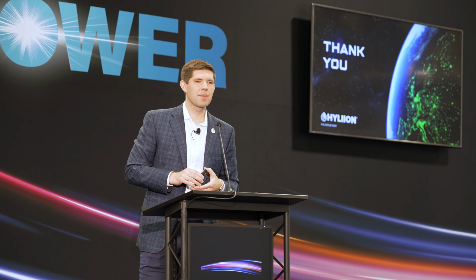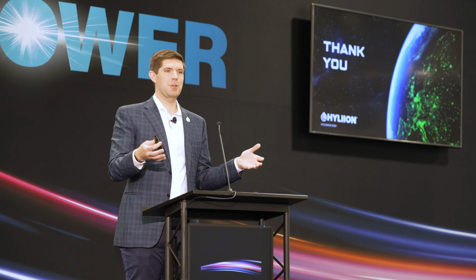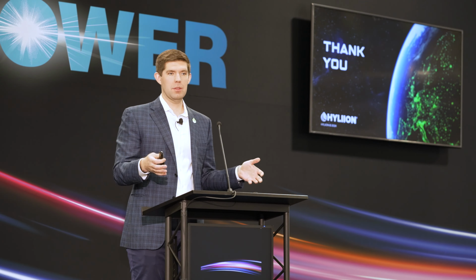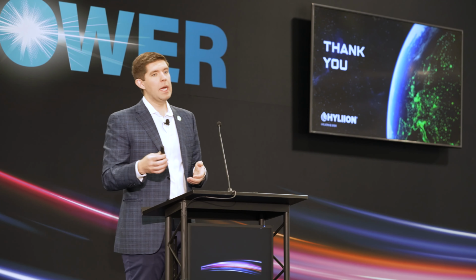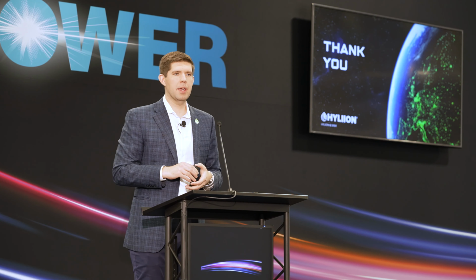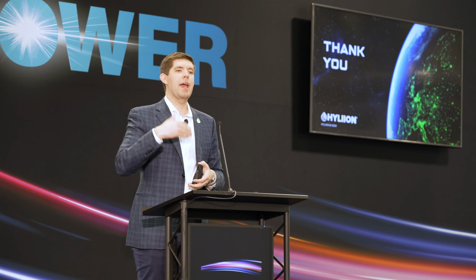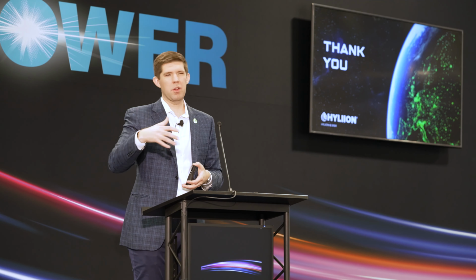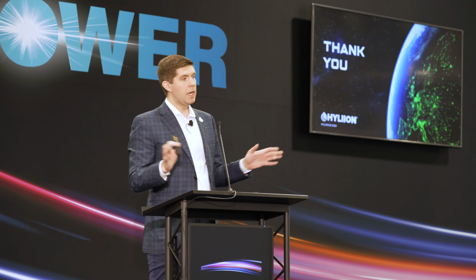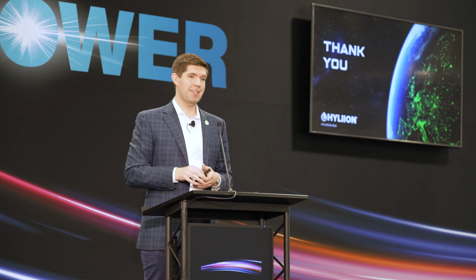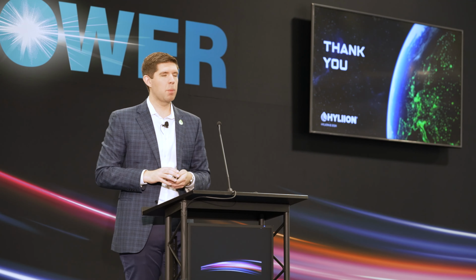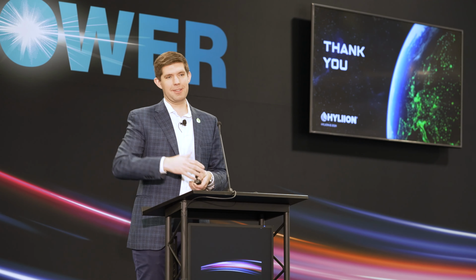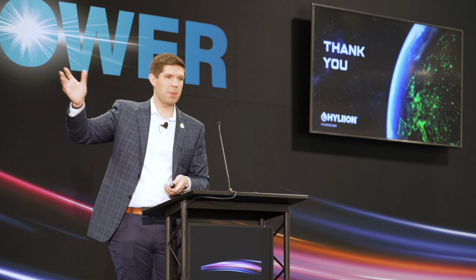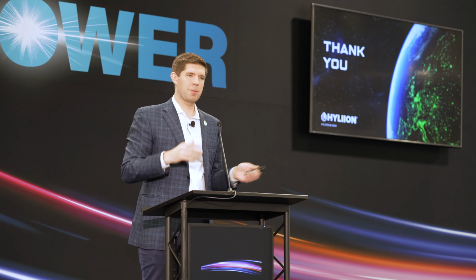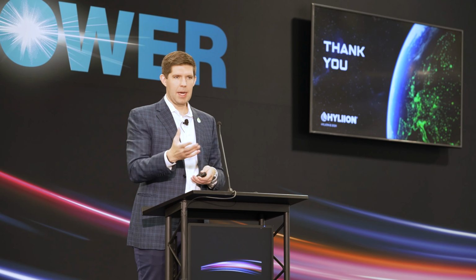Can you speak to the ramping capabilities of the unit? Since our fuel source is heat, if you're starting from cold, it takes a little while to come up—about 30 seconds until we can produce positive power output, and about 3 to 4 minutes until we're at full power output. That's one of the disadvantages. A diesel engine is up and running at full power in about 10 seconds. A fuel cell, like a solid oxide one, takes 30 to 60 minutes until full power. So we're closer to a reciprocating engine in terms of bring-up time, but we are slower.